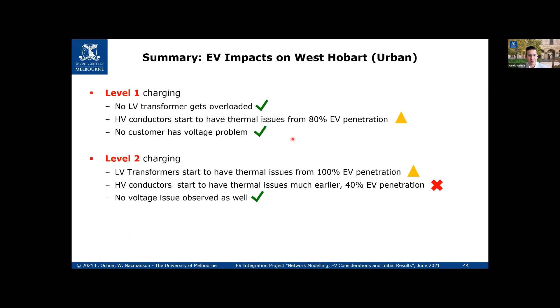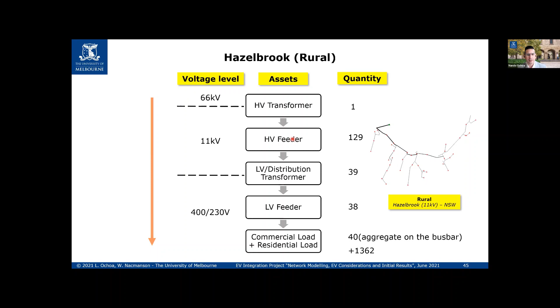Now let's look at a rural network. This is Hazelbrook. When we look at this particular rural network, we're going to see something slightly different. Why? Because in terms of the number of customers it might be similar in total, but they're distributed differently. The feeder is longer because it's rural, and its impedances are much higher. Voltage drops are expected to happen much quicker, or voltage rise if you have solar photovoltaics. But right now we're talking about loads, so the effects are different because this is a different type of network.